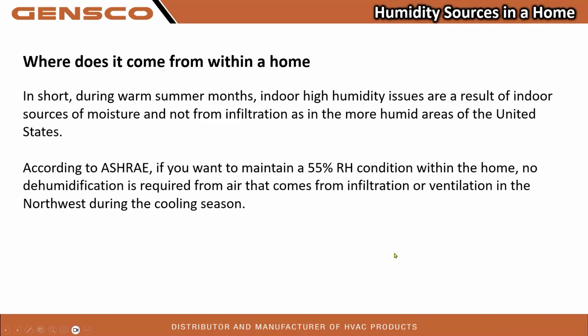And according to ASHRAE, if you wanted to maintain a 55% relative humidity condition within a home, you do not need to have outside air introduced to displace that, because our outside air humidity is so low already. If you want to get to 50%, you will need to remove some physical water.